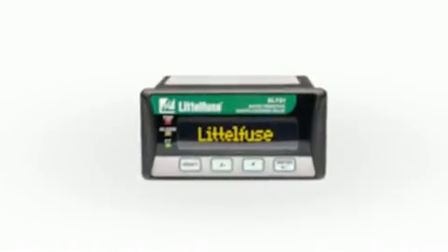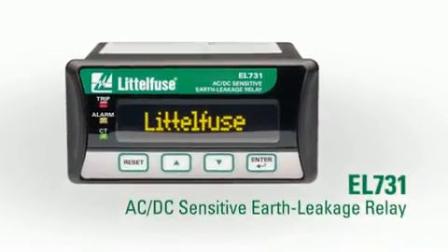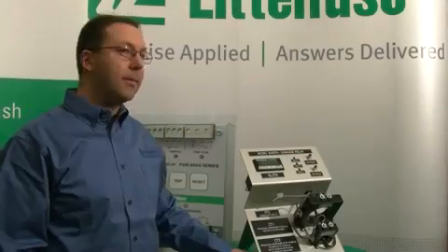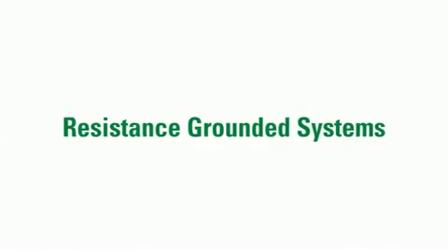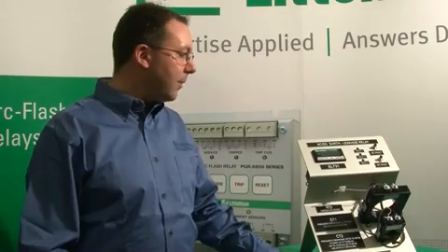I'm Corey Anderson, a sales engineer with Littelfuse, and I'm here today to talk about the EL731 Sensitive Earth Leakage Relay. The EL731 is designed primarily for use in applications that are using variable frequency drives on resistance grounded systems. It's an industry first because it's looking for varying frequencies of ground fault.